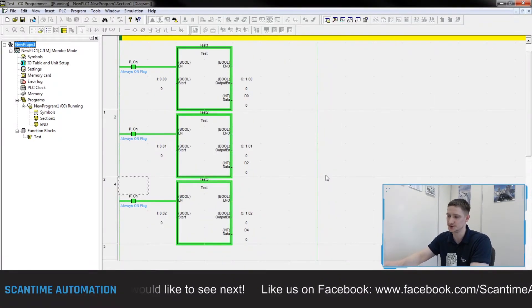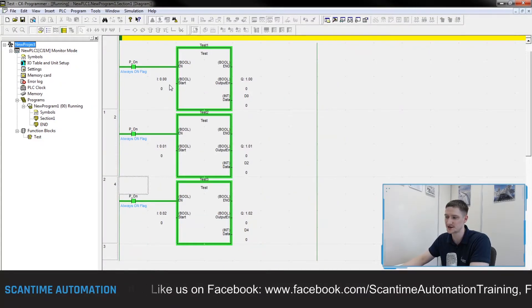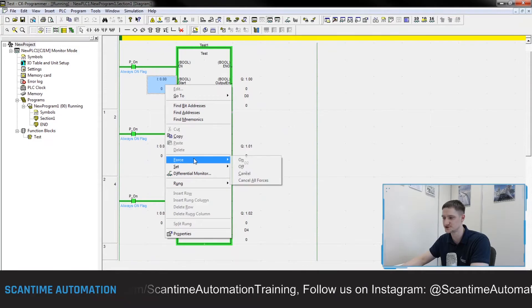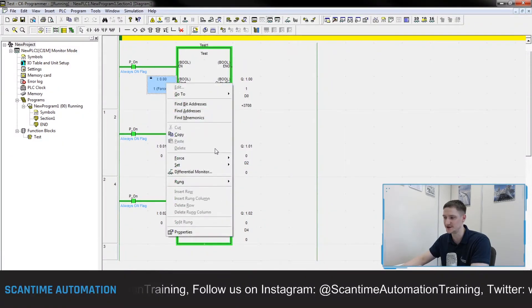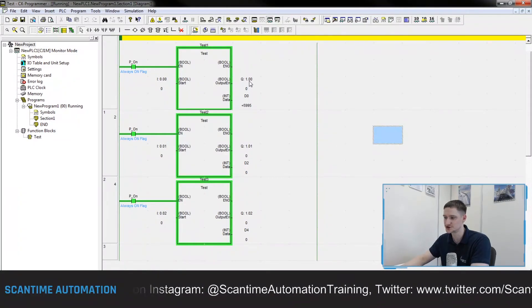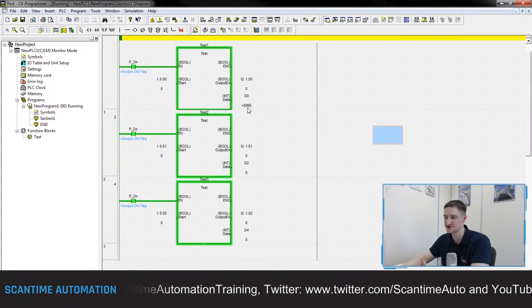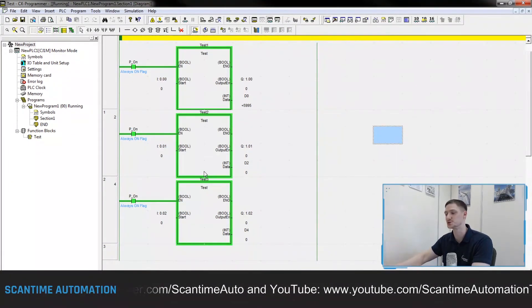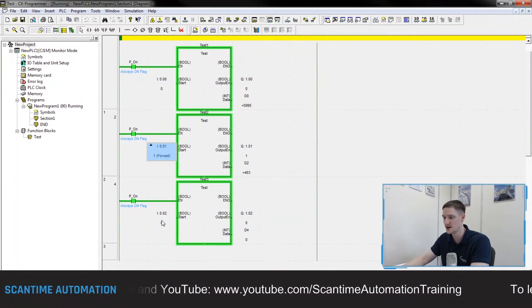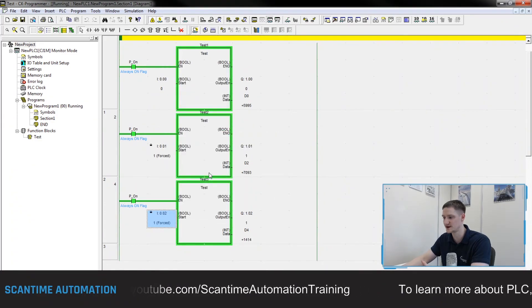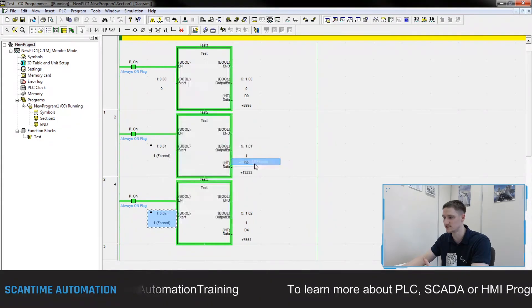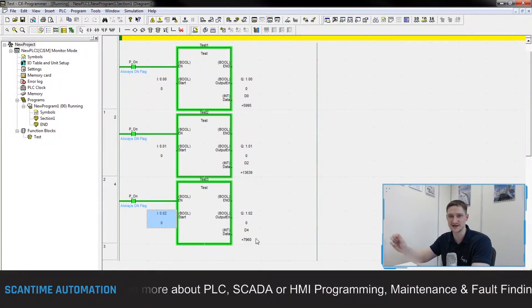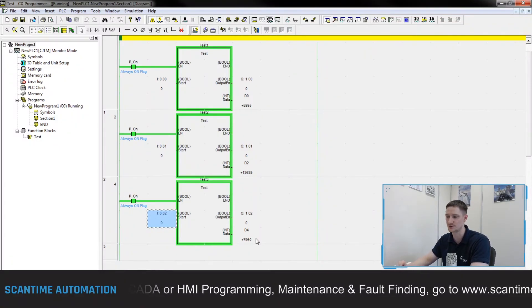Now that it's downloaded, you can see these blocks executing on every scan, though nothing is happening yet because the start signals are not enabled. If I force on the start signal for block one, only that block activates — Q1.0 turns on and D0 increments (it reached 5995). The other blocks are untouched because they use different addressing. I can also force on inputs for the other blocks and have them all running simultaneously.